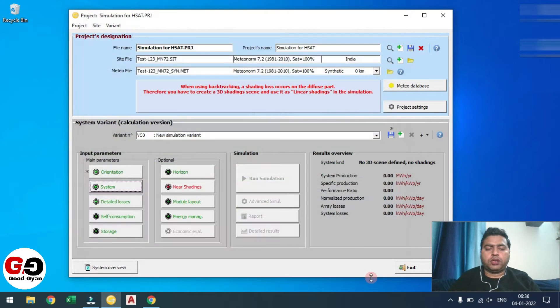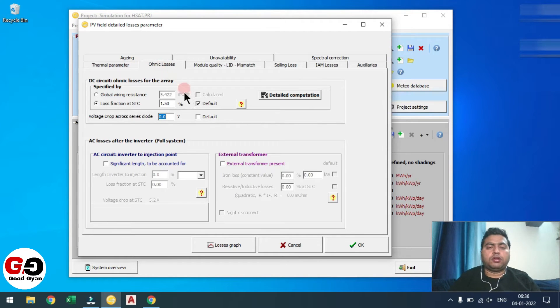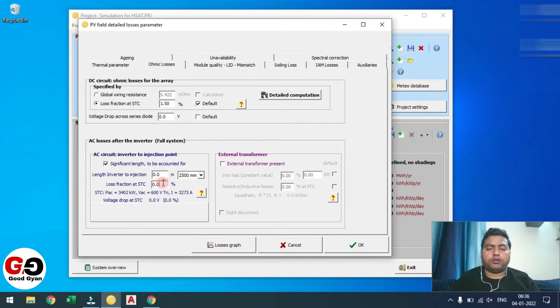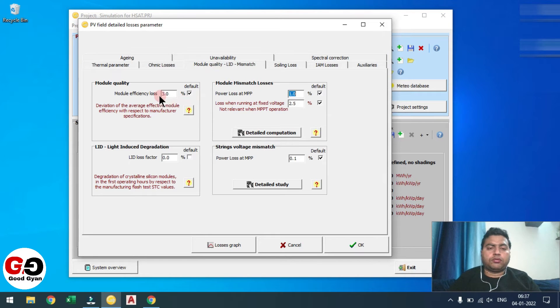Now click on the Detailed Losses page. Select 'Free Mounted Module' because it is mounted with space from the back side. Ohmic loss — we generally consider 1.5% DC loss. Similarly for AC loss we consider 1.2% as a default, but these losses can vary from site to site. Transformer loss we consider 0.5% and 0.2% over here.